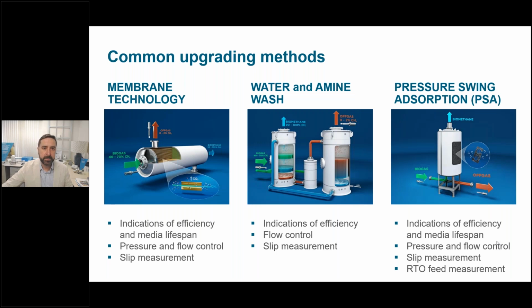Membrane technologies, which I'll get into a bit more, benefit from continuous measurement on the inlet for protection, for recirculation between stages, but just as much for the off gas. Monitoring the methane slip can be an indicator for control and performance, as well as an indicator of when the membrane has reached its end of life. Rather than relying on just volume and time predictions, performance can be measured and assessed by the slip concentration.